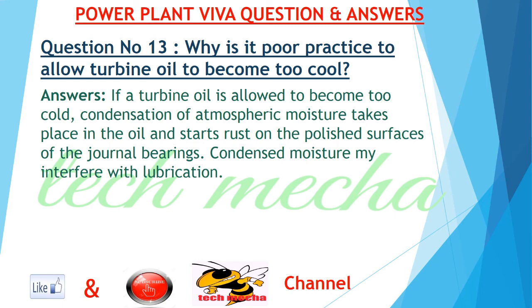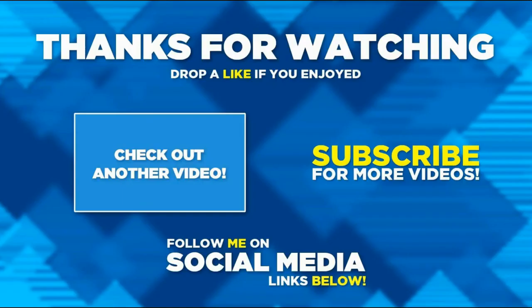Question number 13: Why is it poor practice to allow turbine oil to become too cool? Answer: If turbine oil is allowed to become too cold, condensation of atmospheric moisture takes place in the oil and starts rust on the polished surfaces of the journal bearings. Condensed moisture may interfere with lubrication and with the airtight integrity of the turbine.